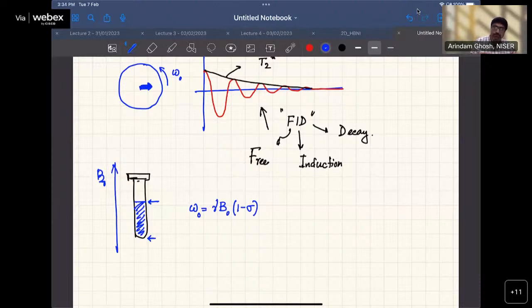But the thing is that in a magnetic field, this field is not really homogeneous. It is not possible to create an absolutely perfect same Tesla everywhere in the sample, because it is extremely high Tesla, 10 Tesla, 16 Tesla magnetic field, which is huge. I have already given you in the second class the average size of the magnetic field in an NMR spectrometer. Like a 400 megahertz spectrometer has almost 10 Tesla. It is just engineering-wise impossible to give you exactly the same B0 over the entire sample. So the B0 will change slightly.